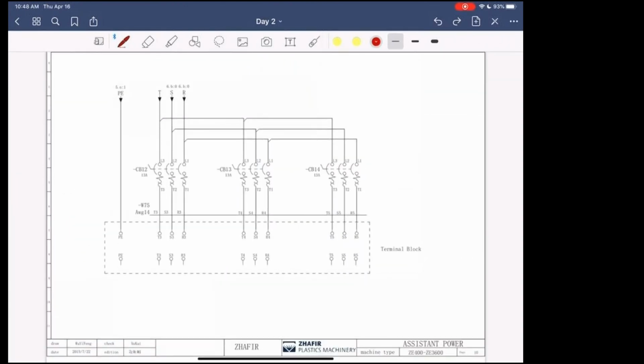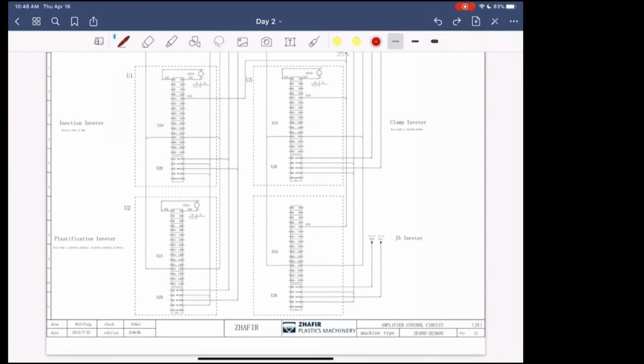All right, here's the one difference. Because it has hydraulics, you have a J5 card. Because of the hydraulics, what you have is a pressure sensor, which is an analog signal. The pressure sensor is 0 to 10 volts. And it needs this J5 inverter signal, which takes the analog signal coming off the machine and converts it to a signal for the KEB drive.